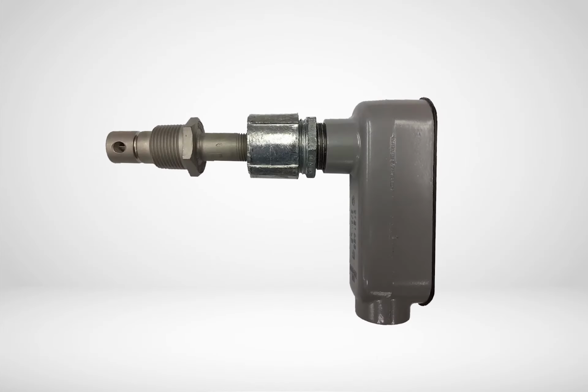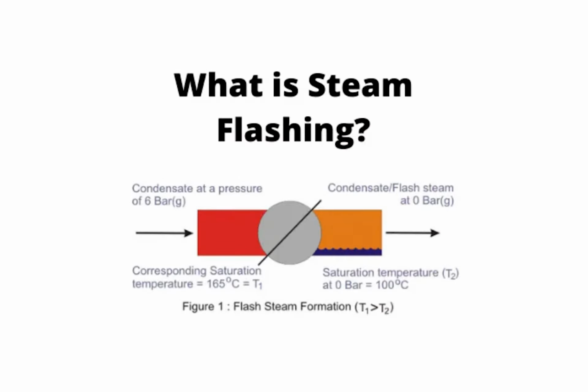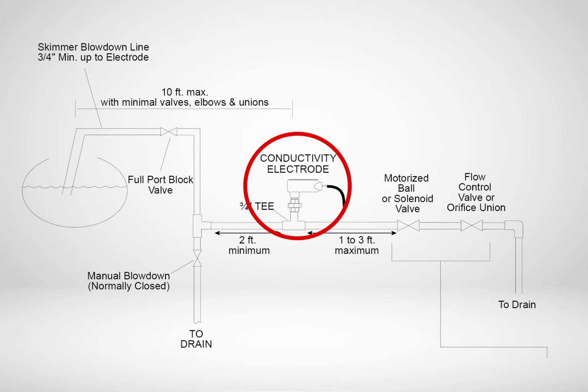Flashing at the sensor is unfortunately very common. Flashing is caused when the superheated water from the boiler sees a sudden decrease in pressure and flashes to steam. The boiler sensor can only read in liquid, so when flashing occurs, the conductivity readings will be lower than actual.